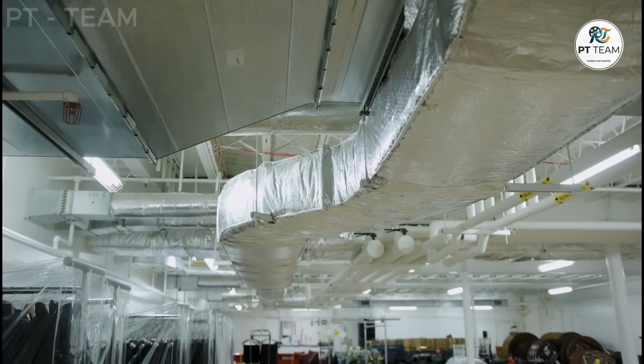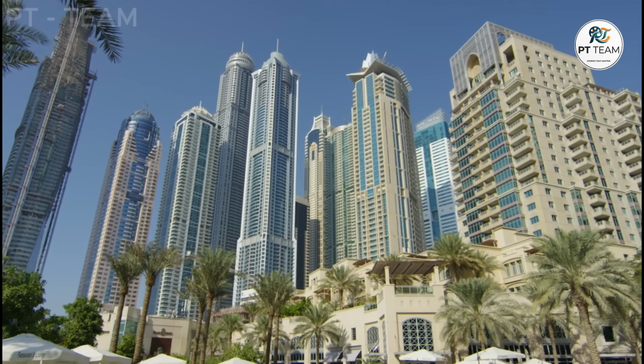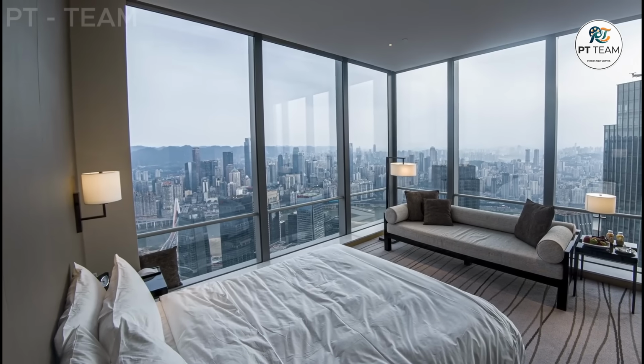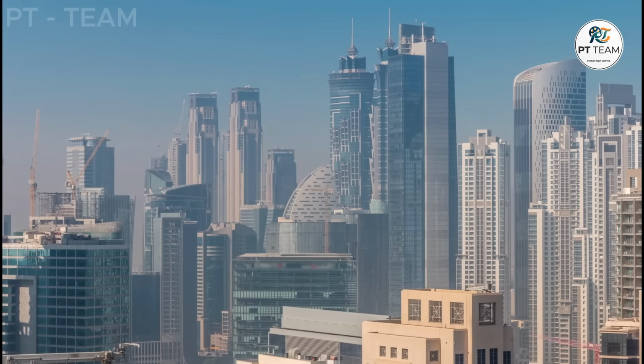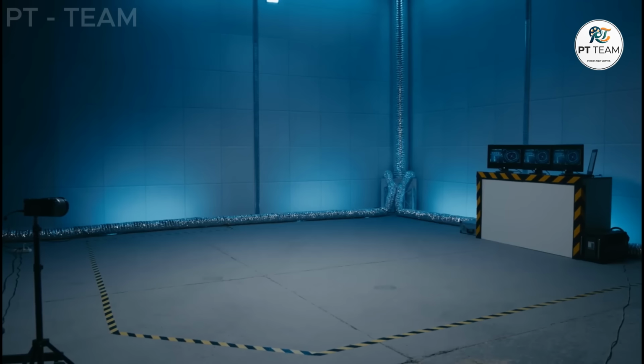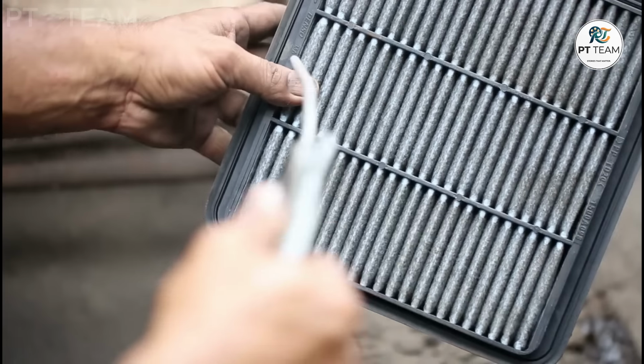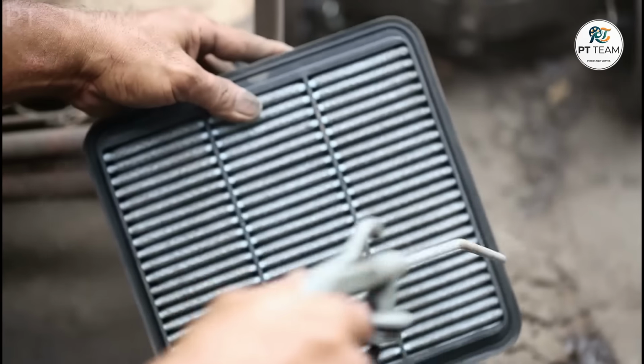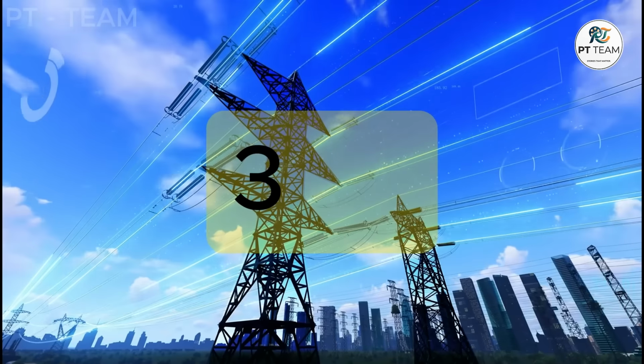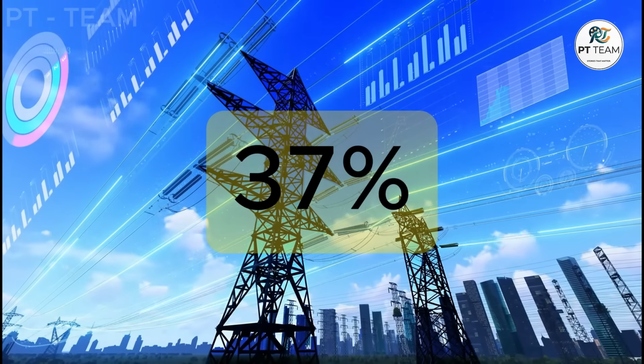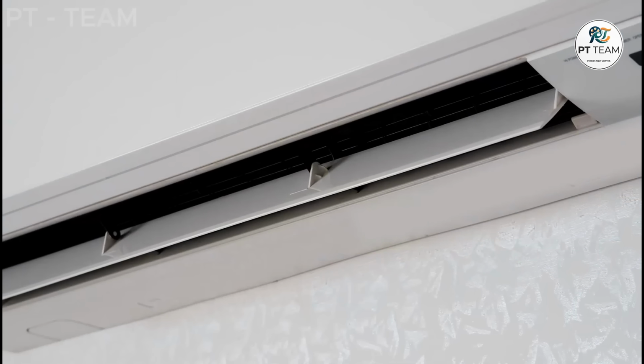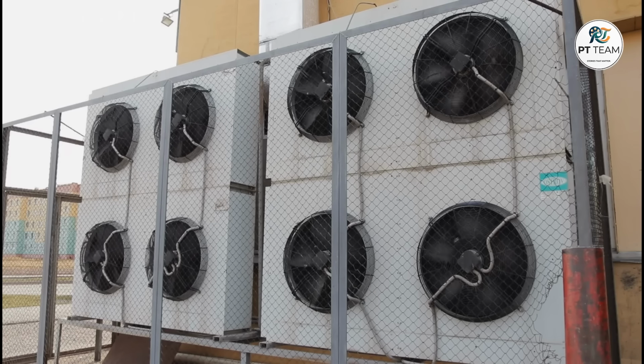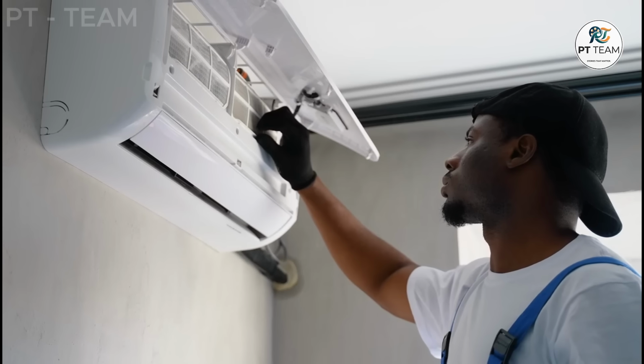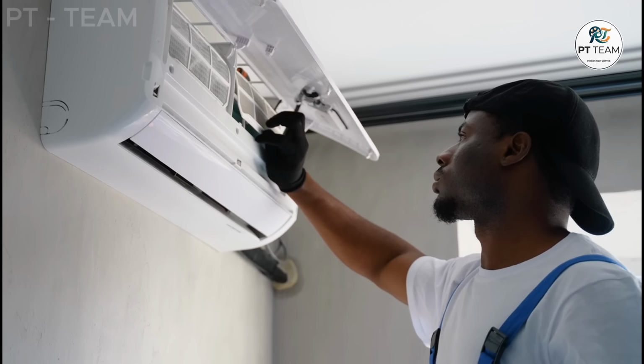ducts is slowly dropping. To understand the hidden pressures on Dubai, we must look beyond the empty hotel rooms or the shifting tourism numbers. We must look at the invisible machinery keeping the entire illusion alive. In one recent engineering experiment, severe filter clogging reduced the net supply airflow of a mechanical system by 37%. The strangest part was that the electricity use did not necessarily rise to warn anyone of the failure. A system can continue to run while its actual capacity to breathe slowly suffocates. When does a protective filter stop being a shield and become a solid wall?